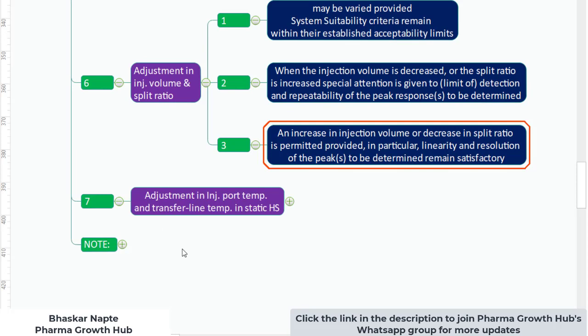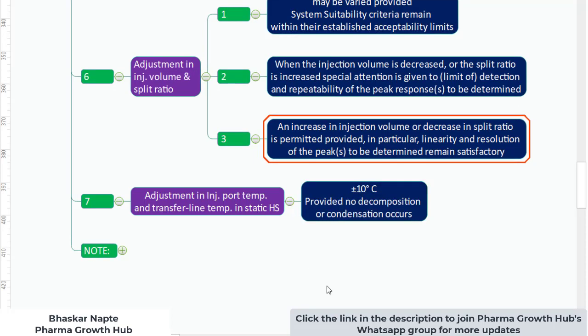The seventh point is adjustment in injection port temperature and transfer line temperature during static headspace. The temperature can be changed by plus or minus 10°C, provided no decomposition or condensation occurs. If you decrease the temperature there is a risk of condensation; if you increase it there is a possibility of decomposition. If neither occurs, you can make the change of plus or minus 10°C to the injection port and transfer line temperature.